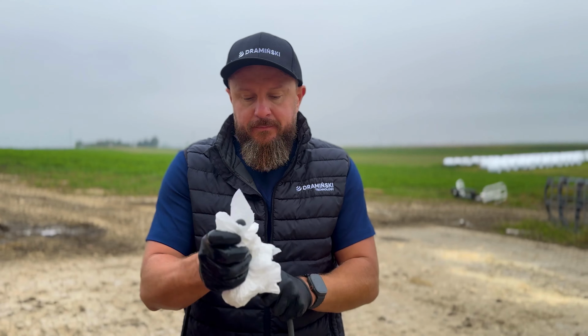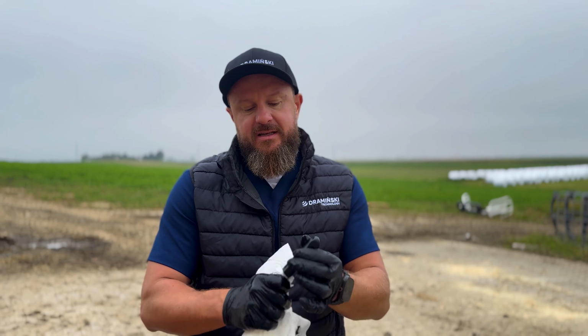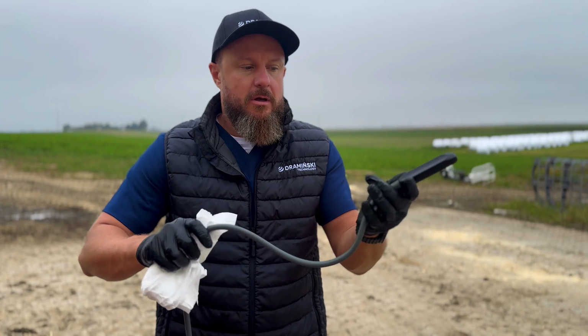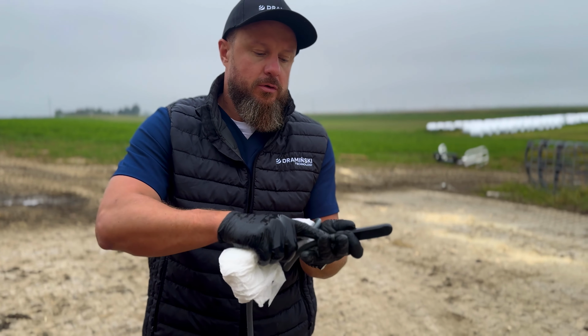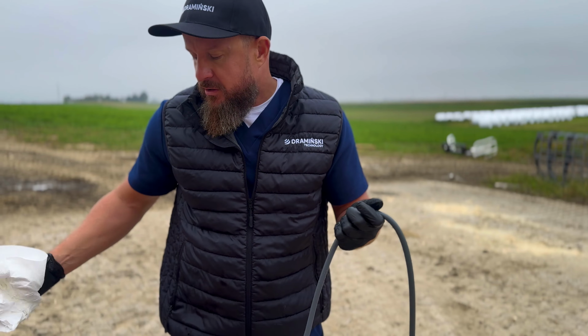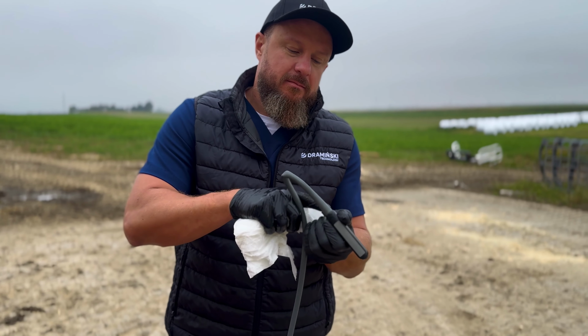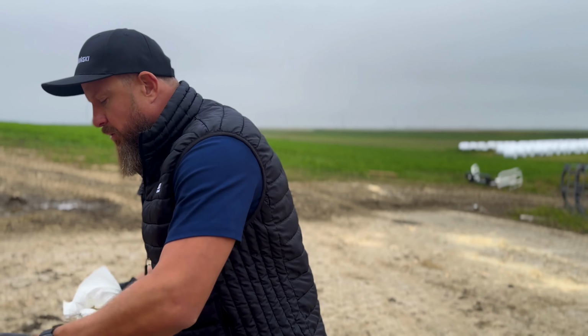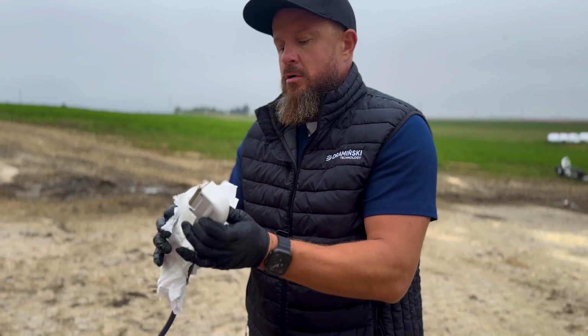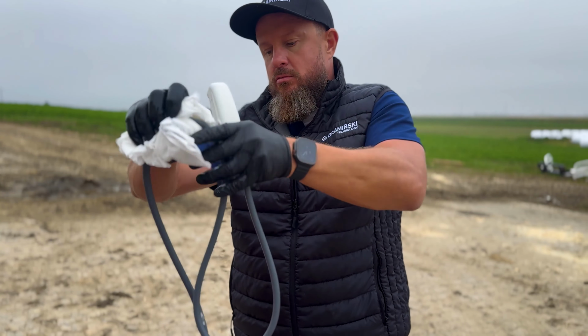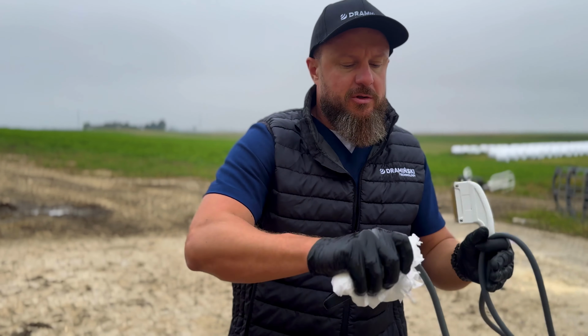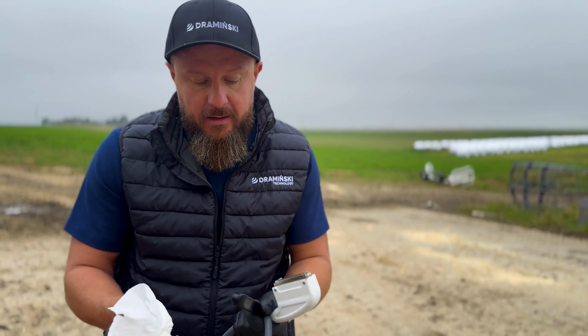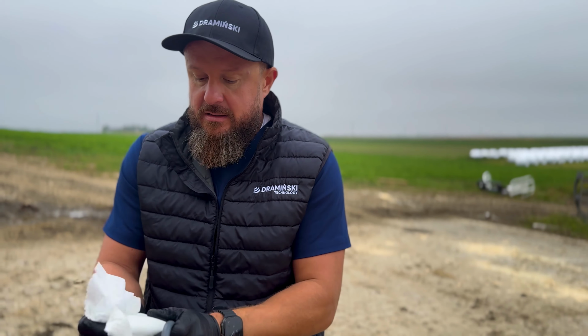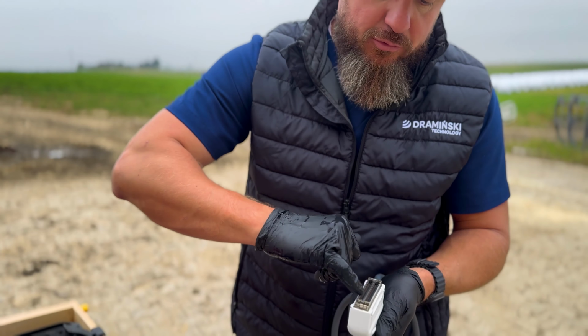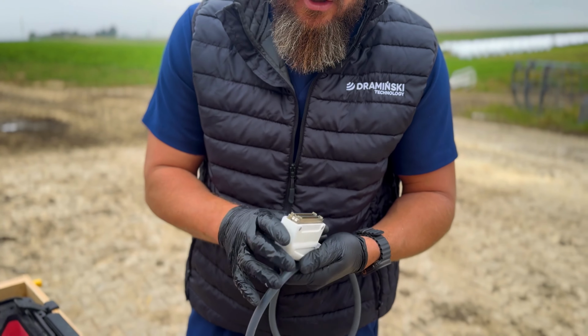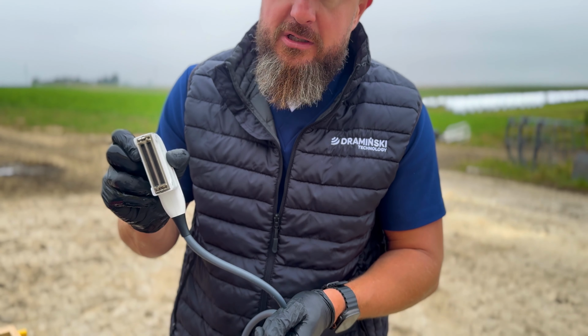Next, we dry the probe. My tip: always wipe it gently, because you can pull the rubber away from the probe. On older models, this part was less secure, so I always wiped from top to bottom. With newer probes, it doesn't make much difference. We also clean the non-waterproof part and check if any water or dirt got inside. This part is also good to blow out every once in a while.